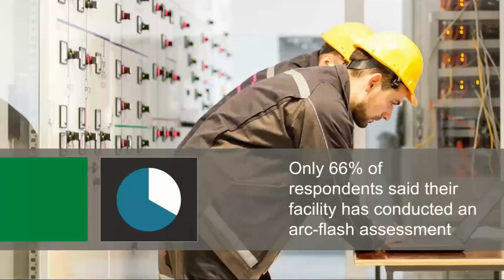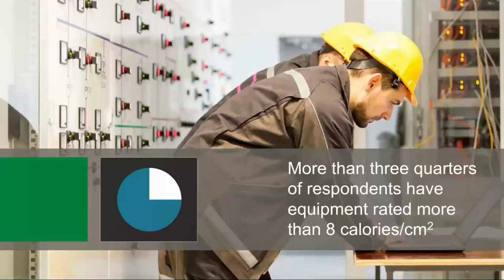It's good to see that, but it really needs to be a higher number. The arc flash hazard assessment is really the first building block of understanding where the risks are, and then from that point you can move forward to try to mitigate those. So that really is a very key first building block. And we'll talk a little bit here about the values that come out of your arc flash hazard assessment. In our survey, about 3/4 of people mentioned that they did have equipment rated at 8 calories per centimeter squared or higher. And really, that's just a line you can draw in the sand, showing that there's equipment with a little more significant risk, where there may be more activities that can be done to reduce that energy and keep it as safe as possible.